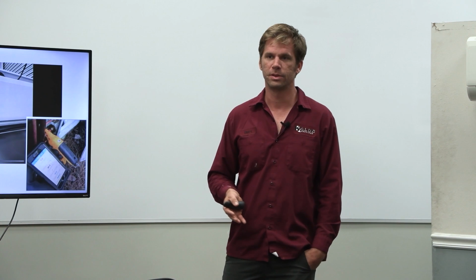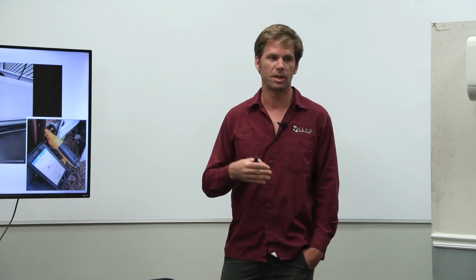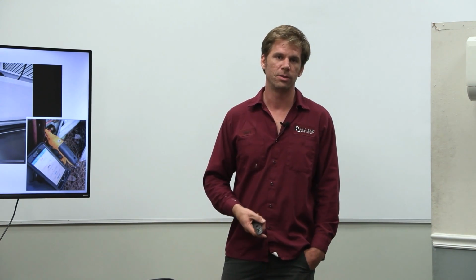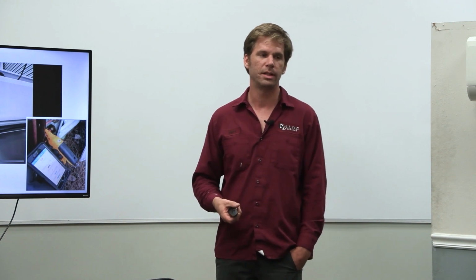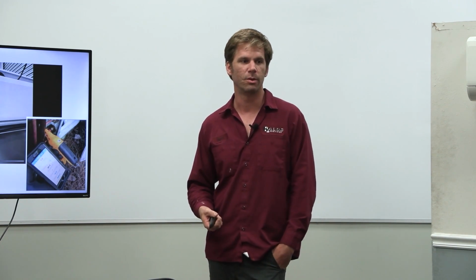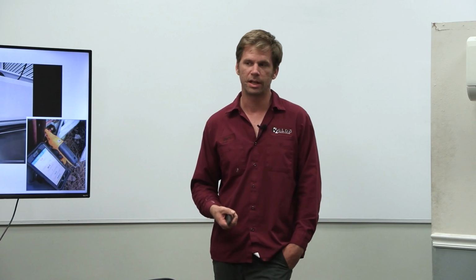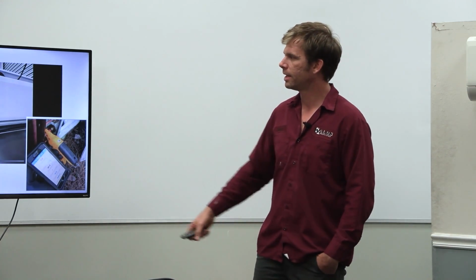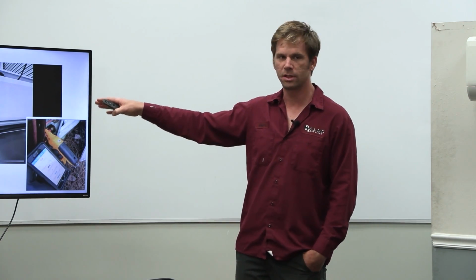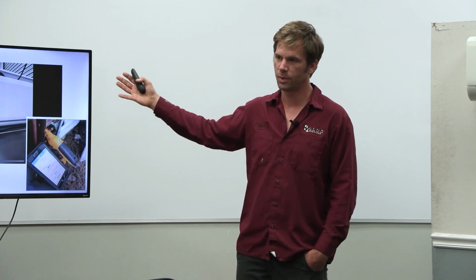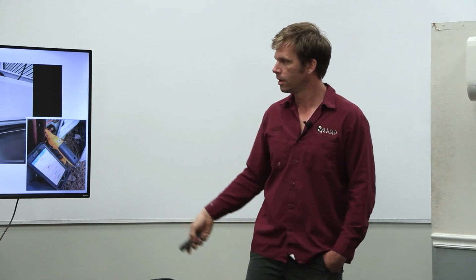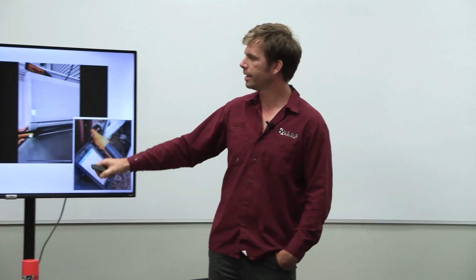You don't want to hook up manifolds and hoses. We've already talked about how much refrigerant that can hold. If you service a system twice a year for 3 years, this thing's going to be low on refrigerant because we've been checking it every time. So with a non-invasive test, we got a great split. We don't have a reason to be concerned. And then the story from the customer is also that it's working good. Great. Red flags. This is when we're going to be hooking up.